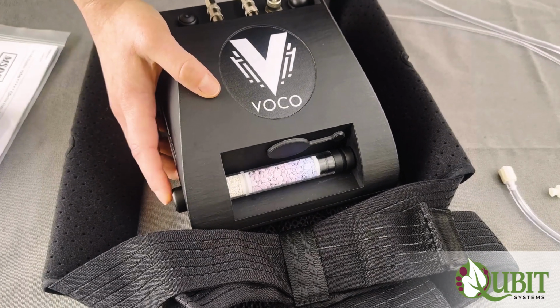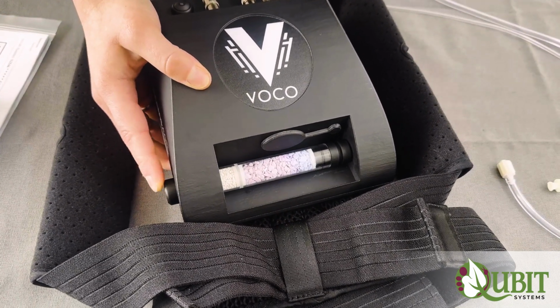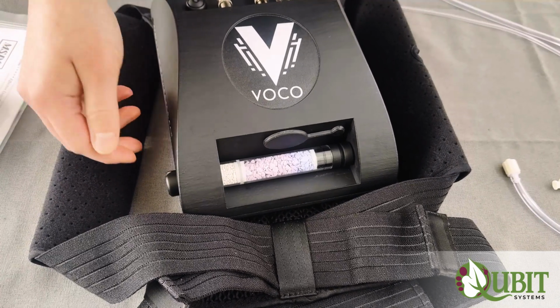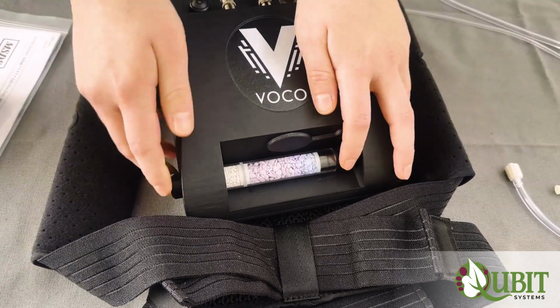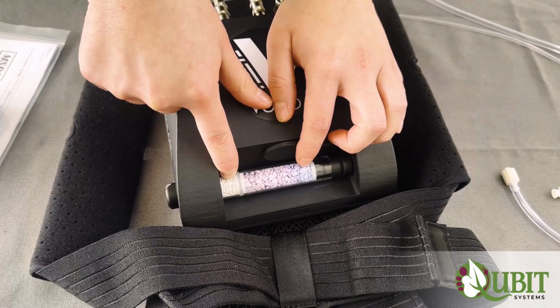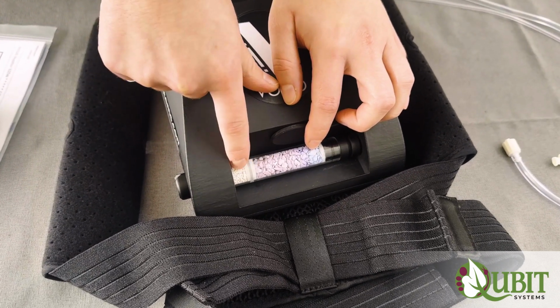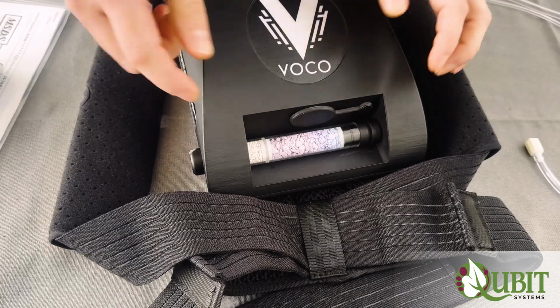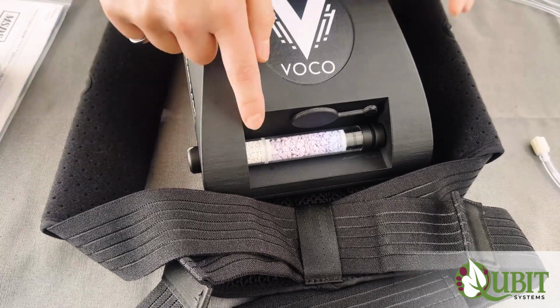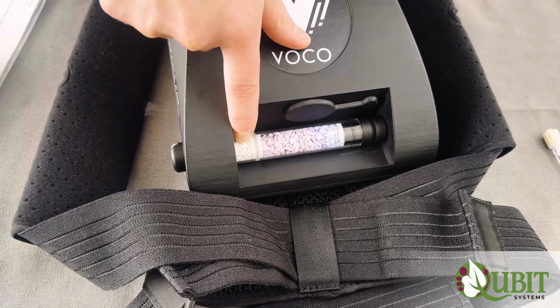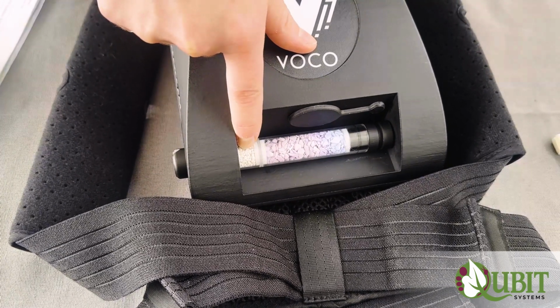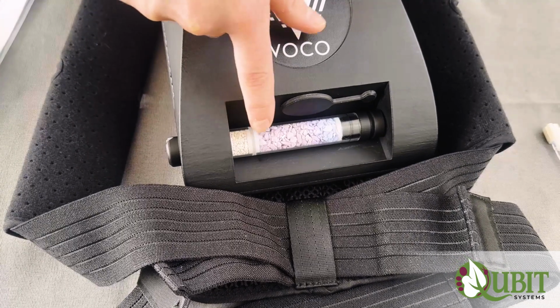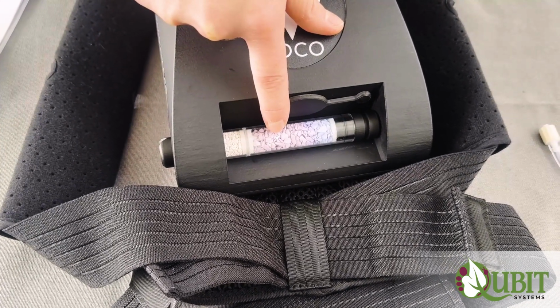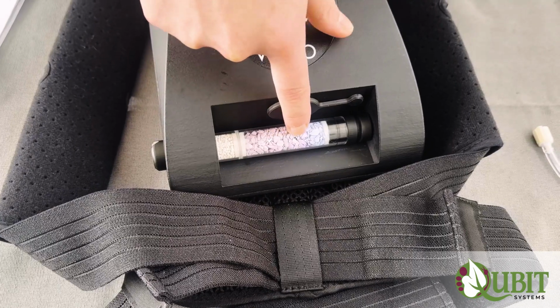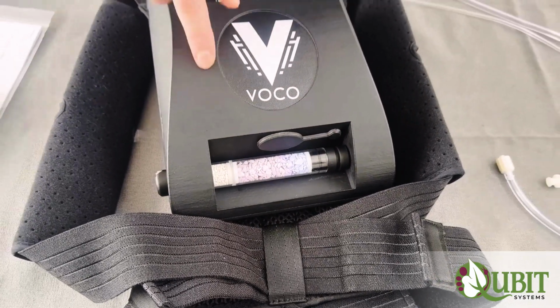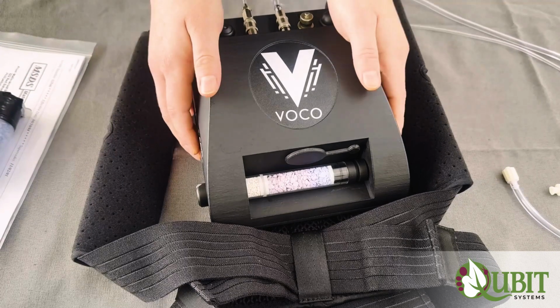It's important to note that this hole must remain unobstructed during use and calibration of the VOCO. During use, it's important to note that the soda lime and the Drierite are placed in their respective locations intentionally. As soda lime reacts with the gas stream and removes CO2, it creates moisture as a byproduct of that reaction. So then the Drierite is able to remove the moisture from the gas stream created by that reaction and then continue to pass dry CO2-free air into the analyzer.